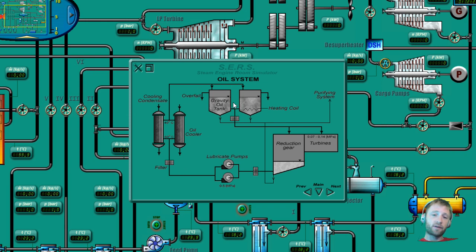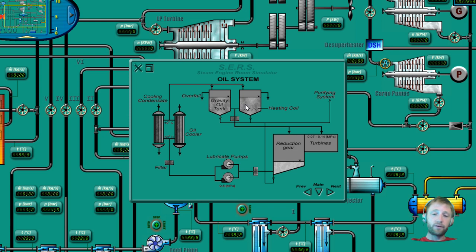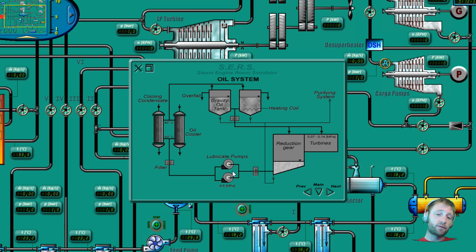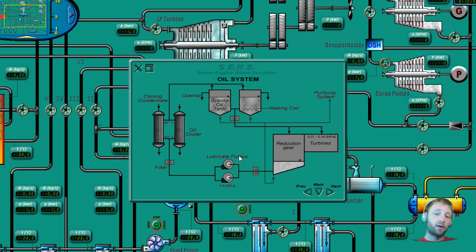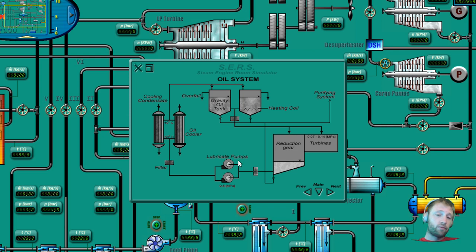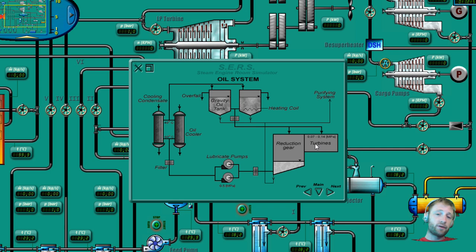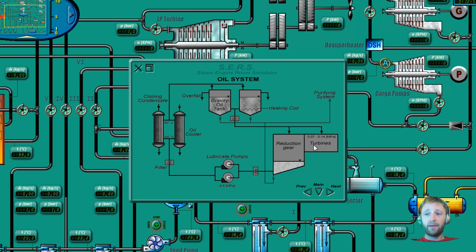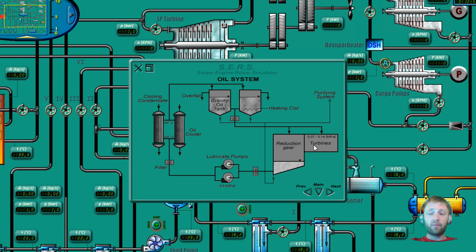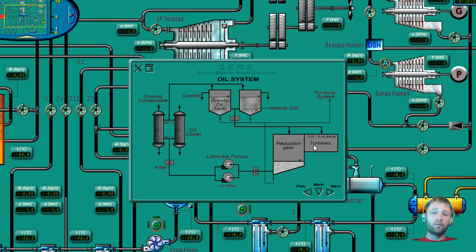So we have also our oil system here, which have some gravity tanks. The gravity tanks were made for the reason that if for some reason our lubricating pumps are stopped or we have some interruption, the oil from here by gravity will lubricate the reduction gear and the turbines because they are turning on high speeds.